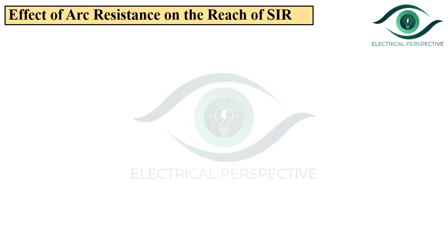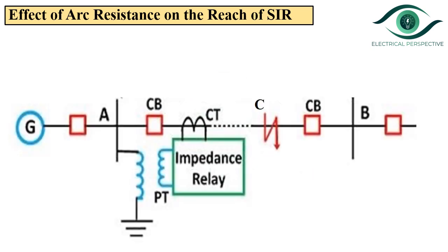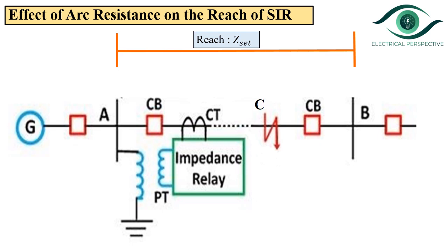Now let us discuss the effect of arc resistance on the reach of simple impedance relay. Consider the transmission line AB as shown in the figure. Assume there is a source only at end A and we wish to create a zone of protection extending from A to B. The impedance relay is located at end A. It requires two inputs: voltage from the PT (potential transformer) and current from the CT (current transformer). The reach of the relay is set equal to Z_set, which is the impedance of section AB under normal operating conditions.